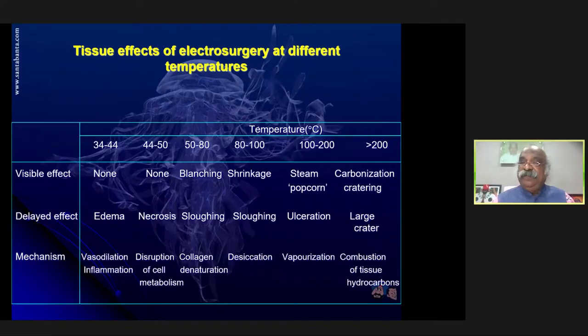You have seen, with inadvertent touch of the electric current to the serosa, to the peritoneum, you see the blanching, the white appearance. That is a visible effect. But the delayed effect is sloughing. That area can give rise to sloughing after a period of days or weeks. At 80 to 100, there is shrinkage of the tissues, and the delayed effect is sloughing. At 100 to 200, there is steam, popcorn effect, and the delayed effect is ulceration. And above 200, carbonization, cratering, and the delayed effect is a large crater because deep infiltration occurs.